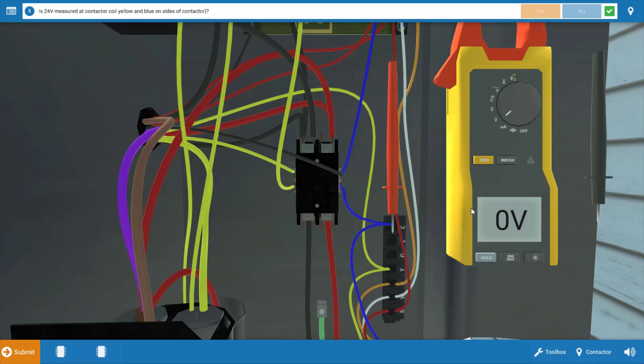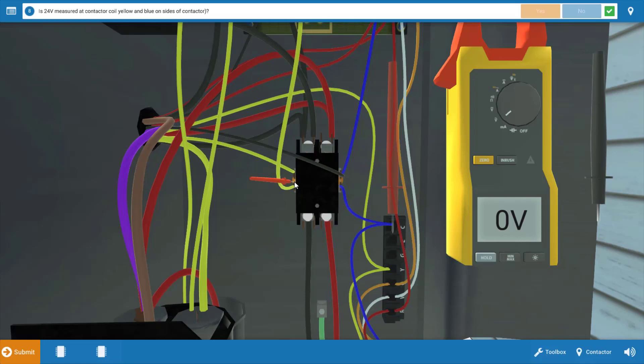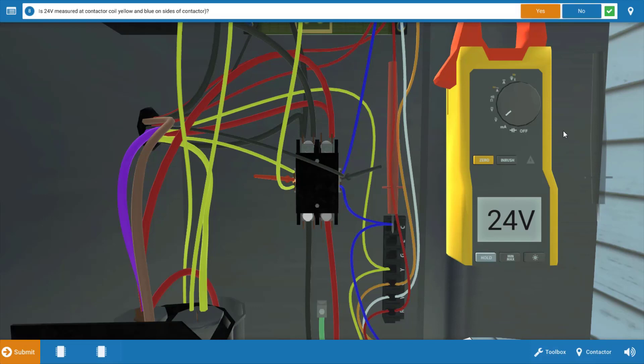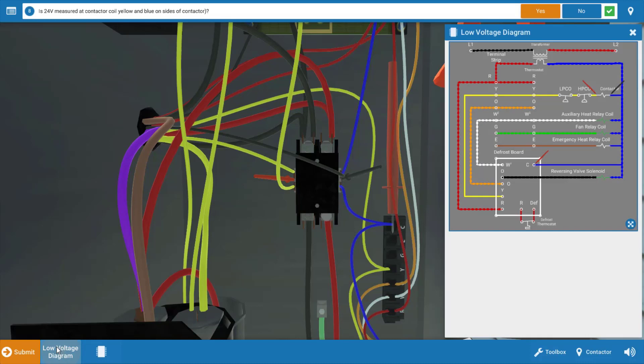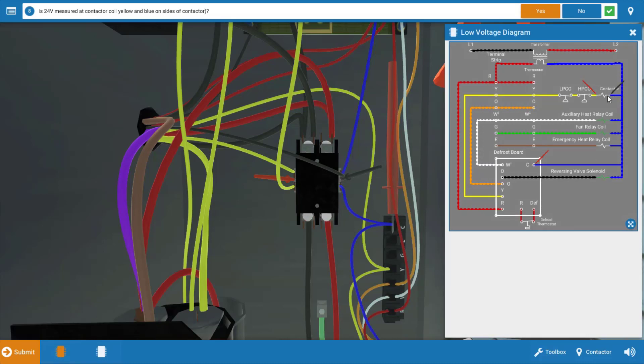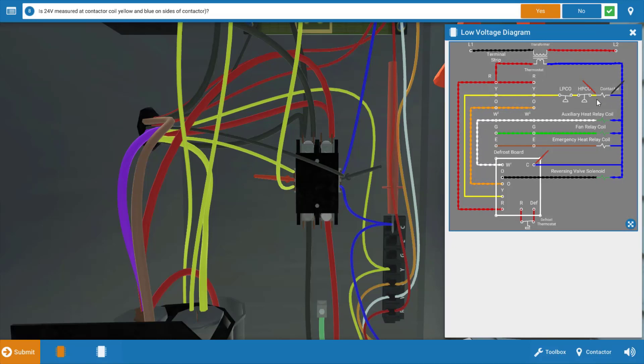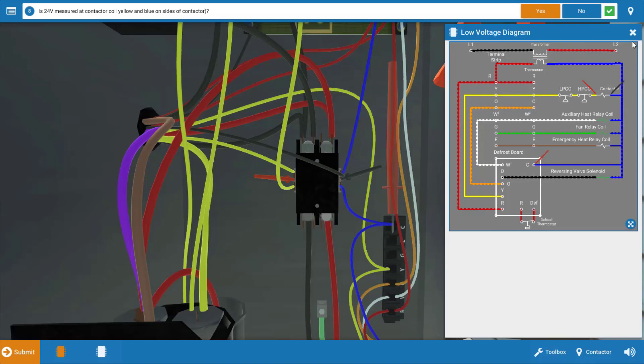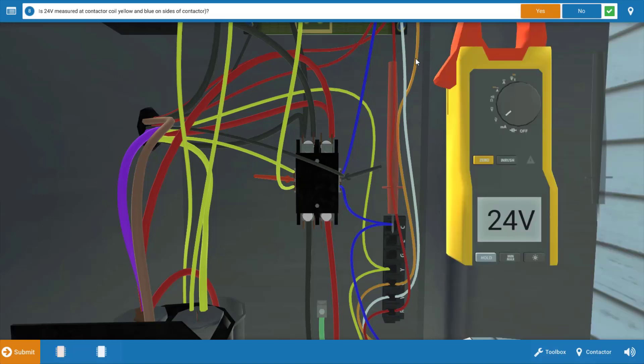So our first step is we're going to measure to see if our contactor is receiving 24 volts. We're going to place our leads on the glowing orange hotspots at the coil connections, at the yellow and blue wire connections. And we have 24 volts to the contactor. Now let's take the wiring diagram out again for just a second. We can see the placement of our meter leads here at the contactor, and we have 24 volts there. What that means is that the thermostat and the two pressure switches are both closed.